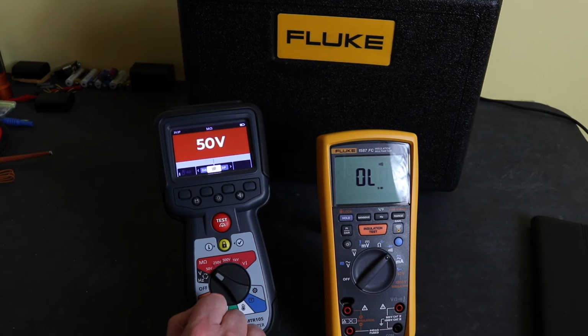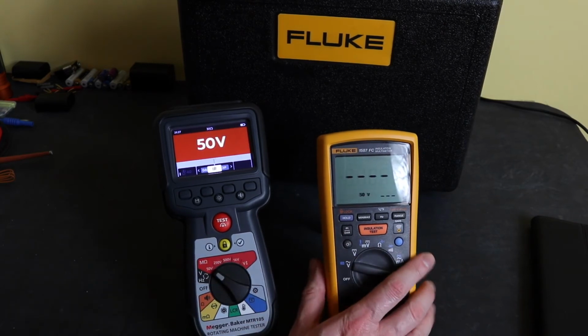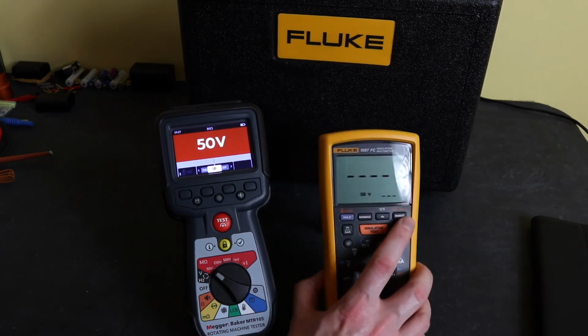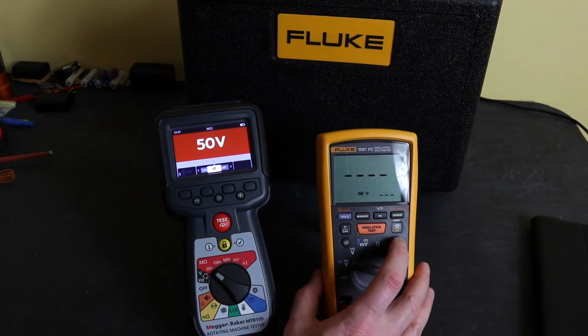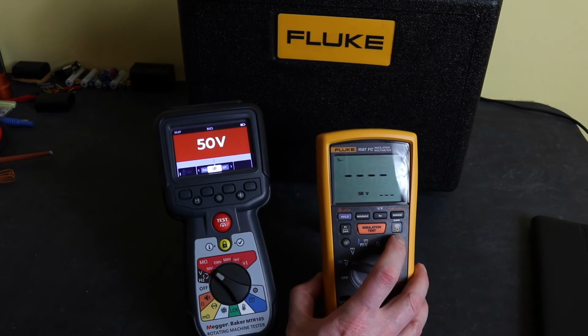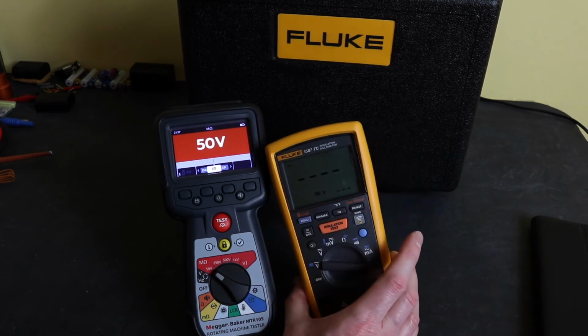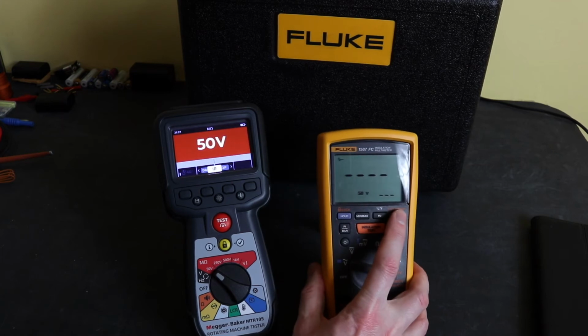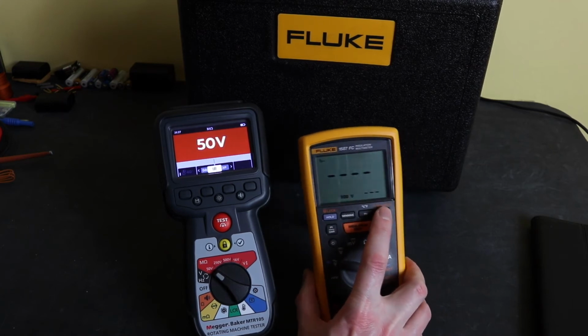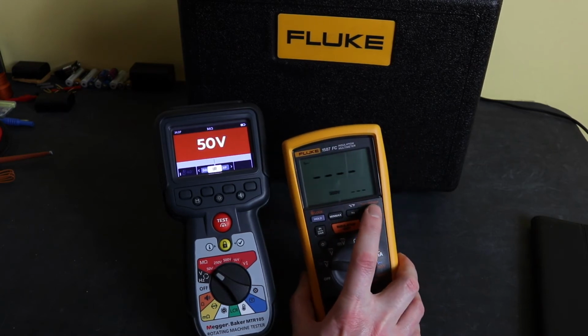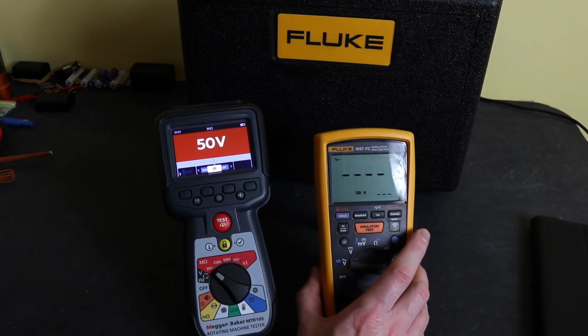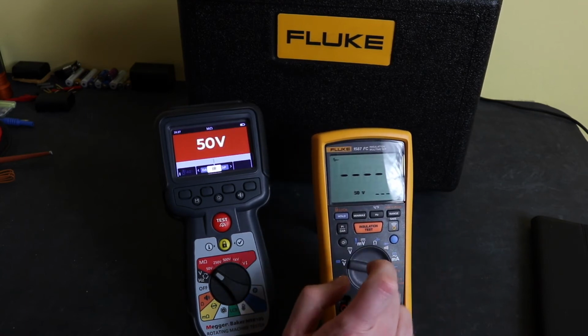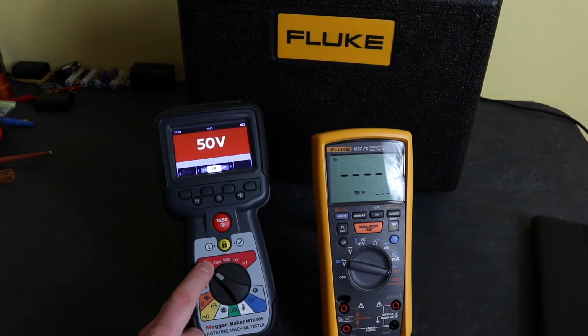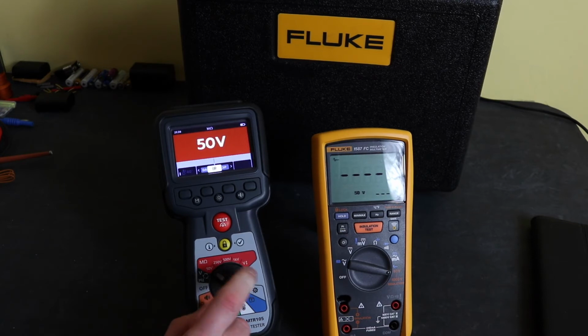Finally, onto the insulation resistance ranges. On the 1587, the voltage selection is through electronic control, which you can press the right one. 50, 100, 250, 500, 1000 volts. They're all the set ranges. You have the 50 volt, 250, 500, 1kV on the function switch here.